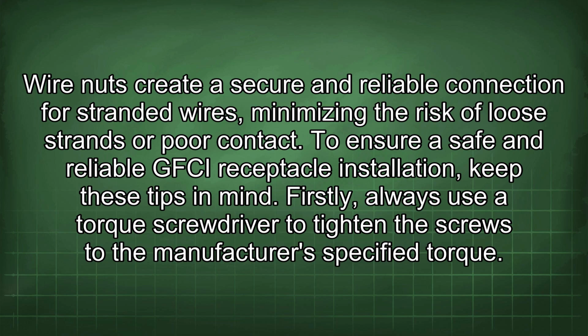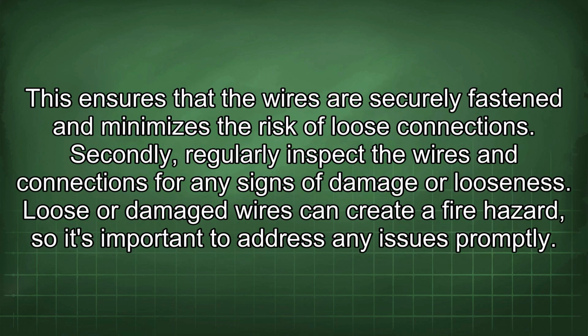To ensure a safe and reliable GFCI receptacle installation, keep these tips in mind. Firstly, always use a torque screwdriver to tighten the screws to the manufacturer's specified torque. This ensures that the wires are securely fastened and minimizes the risk of loose connections. Secondly, regularly inspect the wires and connections for any signs of damage or looseness. Loose or damaged wires can create a fire hazard, so it's important to address any issues promptly.